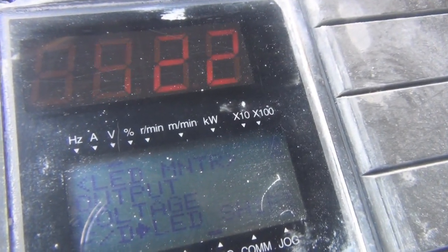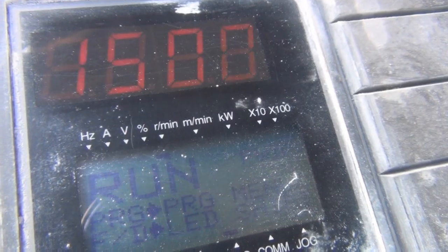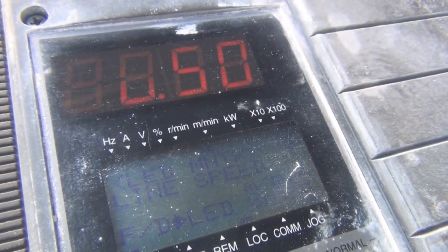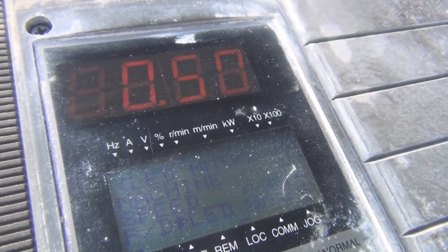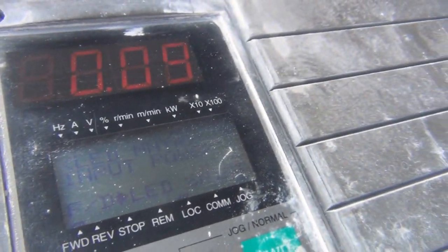Output current, output volts, motor speed — wonder if that detects the RPM of the motor somehow. Line speed — that'd be 50 hertz I'd say. Machine speed. Kilowatts — 0.09, oh that's cool, it even measures the power in kilowatts.